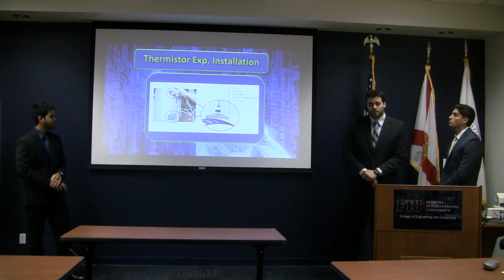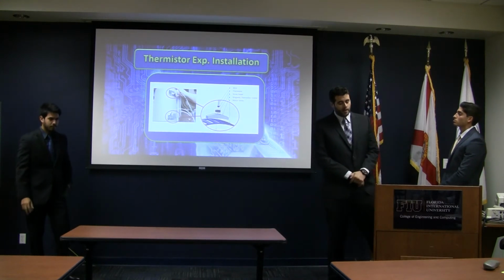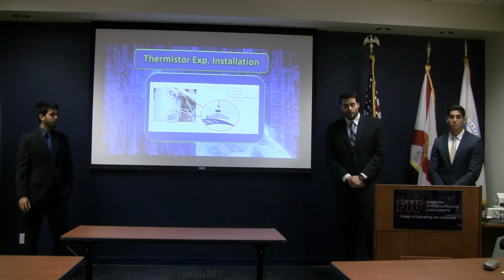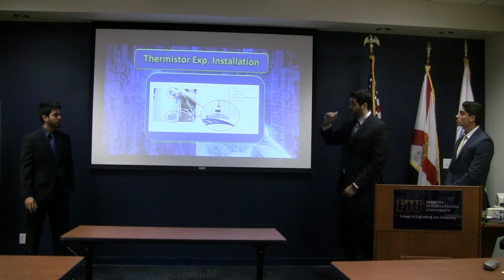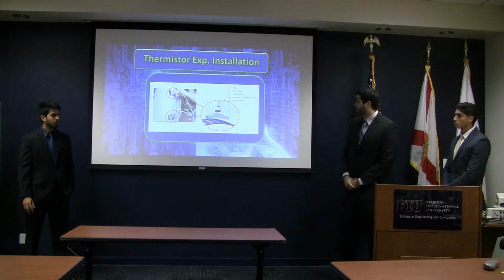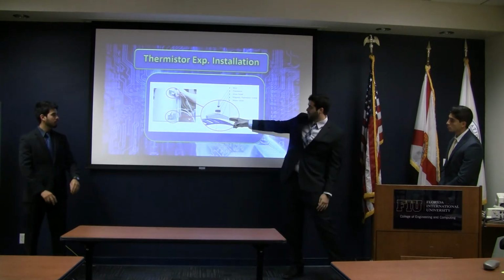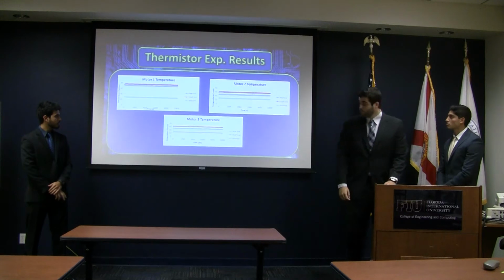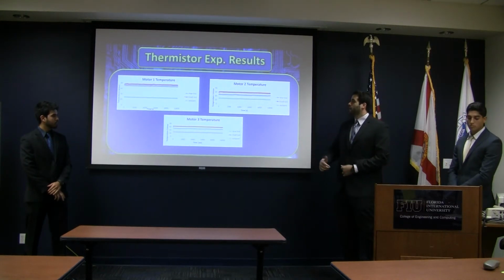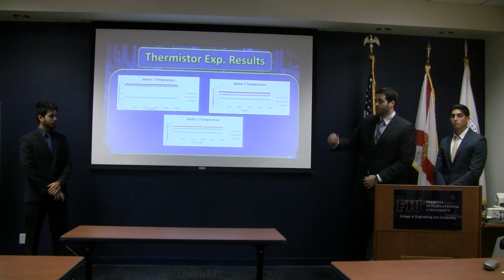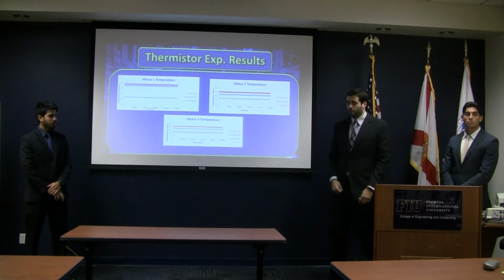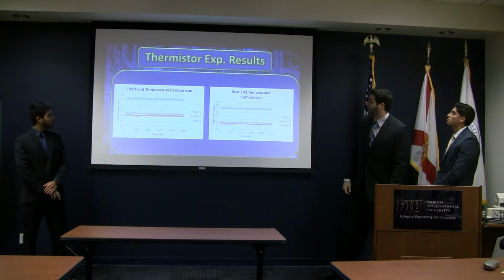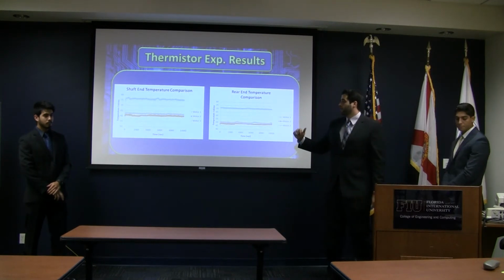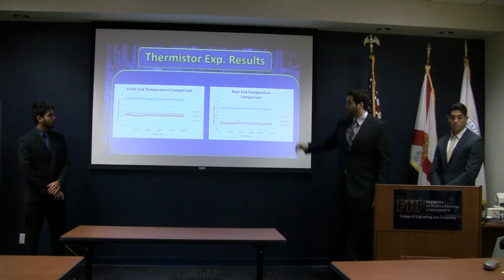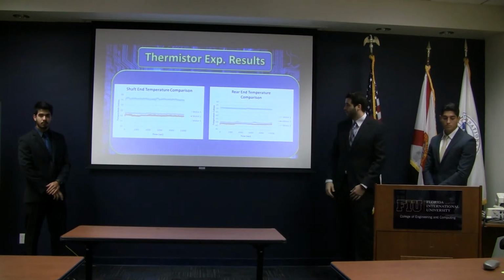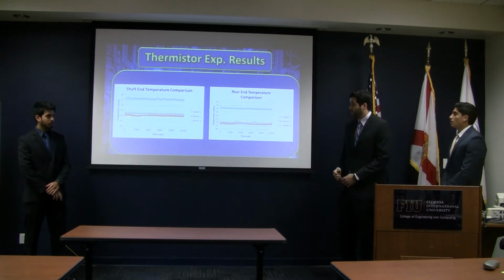So to do the install for the thermistor experiment, we created a magnetic thermistor holder that goes over the motor's vents, as you can see here, but does not obstruct the vent. And then we place the wire through there with the thermistor connected and with the strain relief. Here we have the three motors where we did the rear end and the shaft end, and then we recorded the ambient temperature. And then here we compared the shaft end and the rear end. As you can see, motor 1 has a higher temperature, so our system proves that the motors run at different temperatures and will show faults.